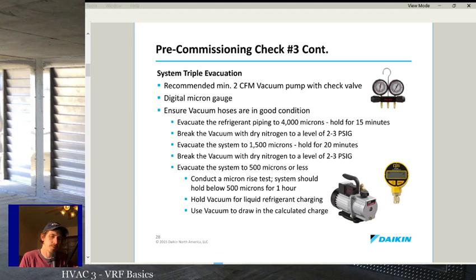So you make sure that you put the piping together without having any dirt or debris get into the system, and then you make sure that when you're done, you evacuate the system completely, have no moisture in there, you have no leaks. Having a good vacuum hold for a long time basically double ensures after your pressure test that you don't have any leaks, and you end up with a system that should hopefully never need to be opened up for service until a component fails for some other reason.